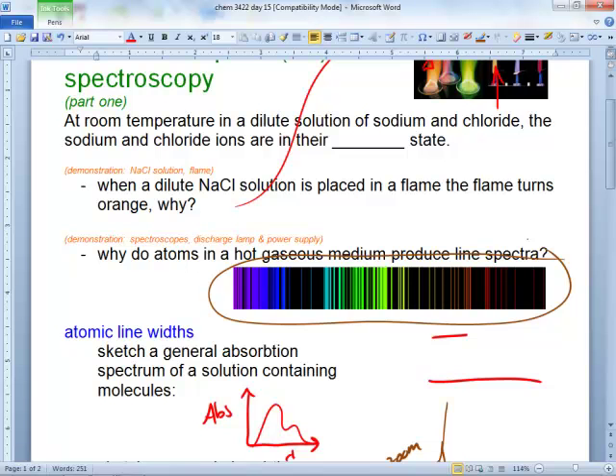Sodium lamp, right? If you want to analyze for copper, you have to have a copper lamp. Copper absorbs copper light, so you have to have a copper lamp. So I'll just say that's copper. Well, you go to the AA cookbook, and it says, in this range, this slit width, and all this, it wants you to use this wavelength right there. I'm just picking it, for whatever reasons.